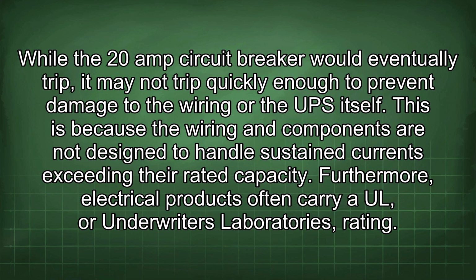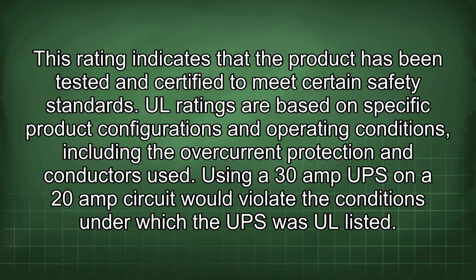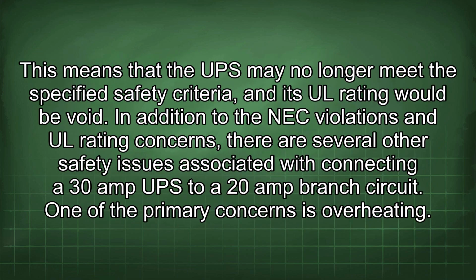Furthermore, electrical products often carry a UL, or Underwriters Laboratories, rating. This rating indicates that the product has been tested and certified to meet certain safety standards. UL ratings are based on specific product configurations and operating conditions, including the overcurrent protection and conductors used. Using a 30 amp UPS on a 20 amp circuit would violate the conditions under which the UPS was UL listed. This means that the UPS may no longer meet the specified safety criteria, and its UL rating would be void.